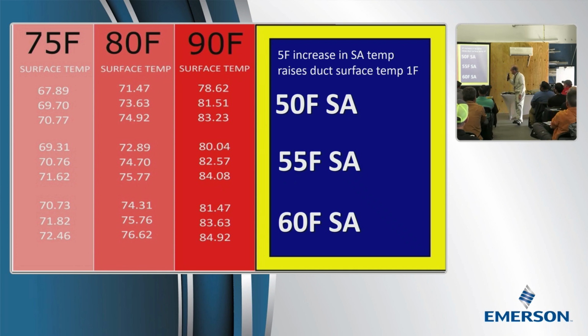Well, the only thing he can do is raise the fan speed, right? Doing it for years. It's sweating. I guess we'll raise the fan speed. Even though we really wanted to design it with a low fan speed, and that was the best scenario for what we were doing, we end up selecting a fan speed just so we don't rain on the duct. So it's a heck of a compromise, but it's the only thing that a service tech can do. What's a service tech going to do? Pull all the duct out on a service call? So he hasn't got a lot of choices.